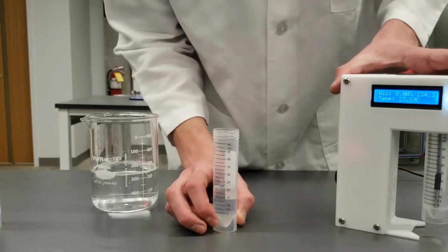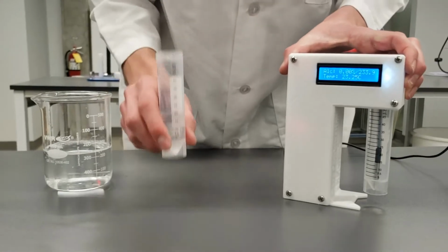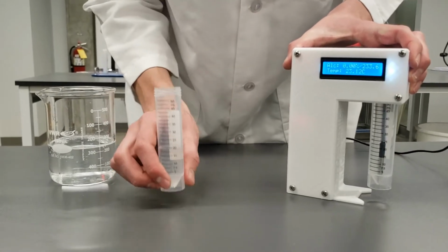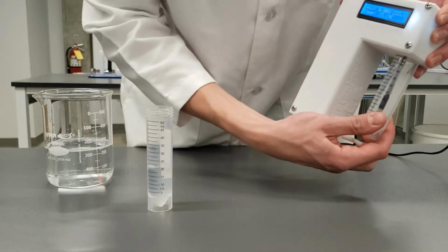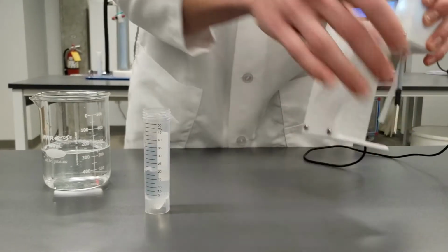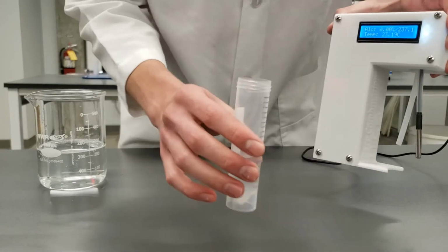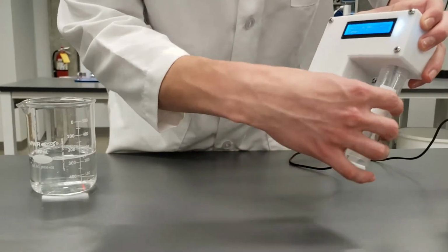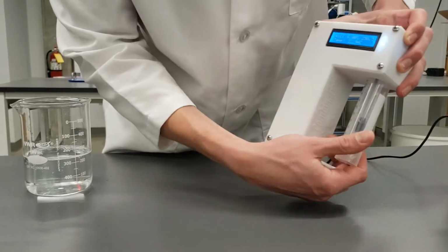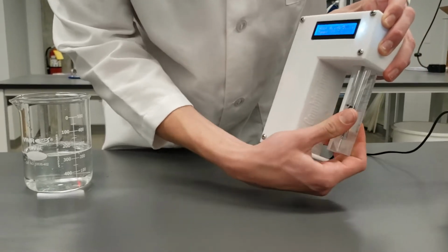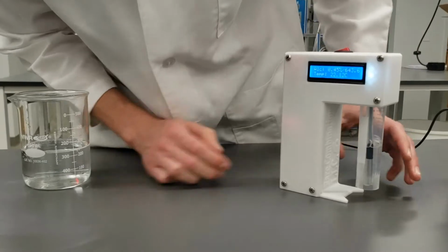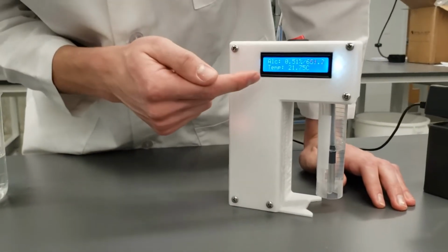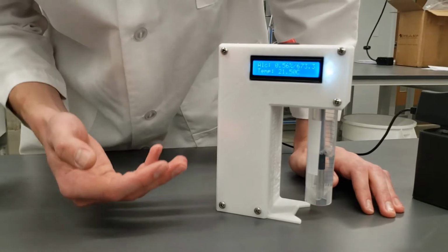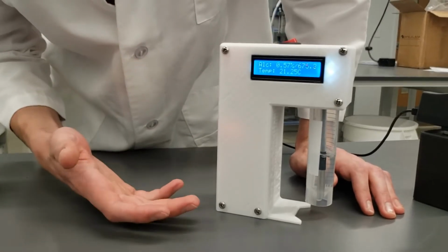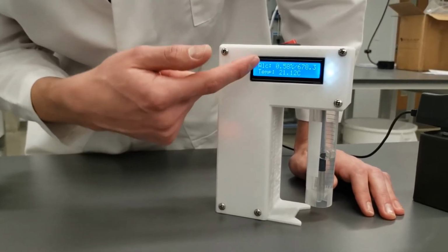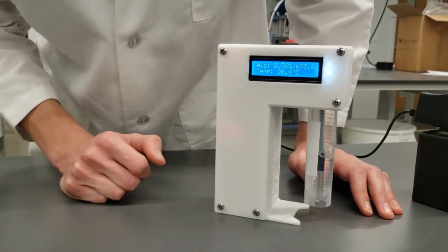So since the detector is warmed up and we have our 0.5% alcohol content standard at room temperature, we're going to unscrew our air tube, set that to the side, and we're going to screw in our 0.5% sample. So if we're really lucky, it will read 0.5% alcohol content on the very first try. However, that's probably not going to be the case. As you can see now, it's probably going to read about 0.6% alcohol content.